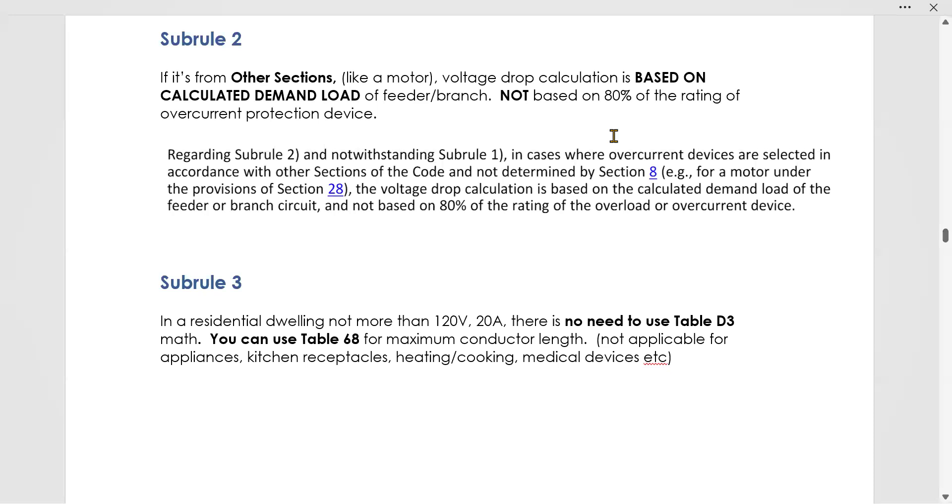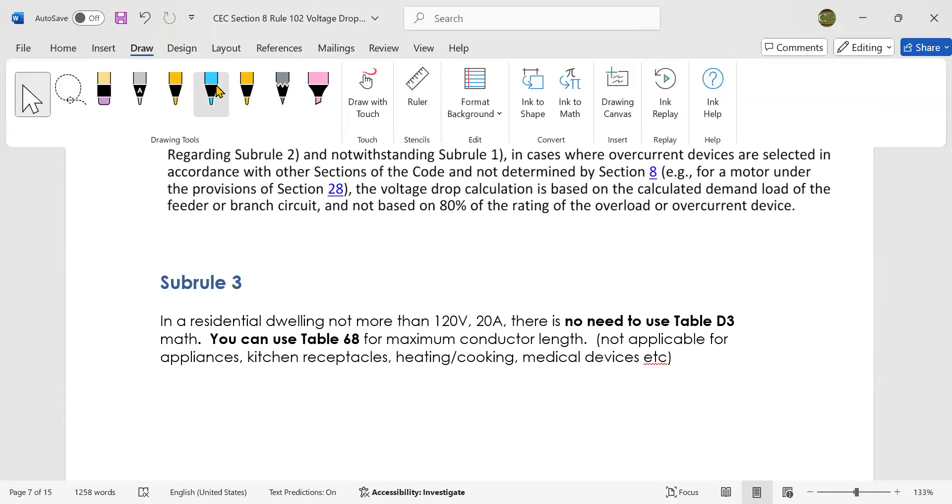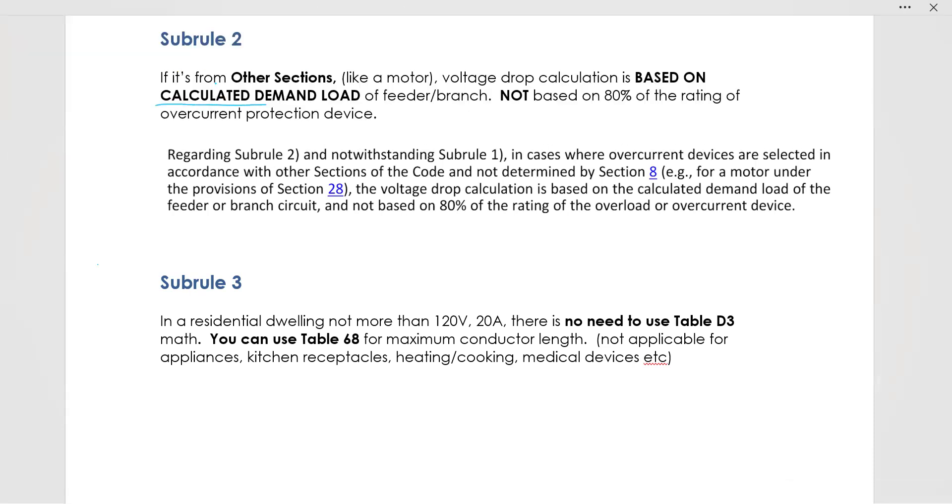Subrule 2 of 8.102 says that if you're from other sections, for example, like the motor section, then the voltage drop calculation can be calculated based on the demand load. It can be calculated based on the calculated demand load of the feeder or branch, not based on 80% of the rated over current protection device. All right. So you have to know if you're coming from other sections, then you can use subrule 2. Thank you for subrule 2.